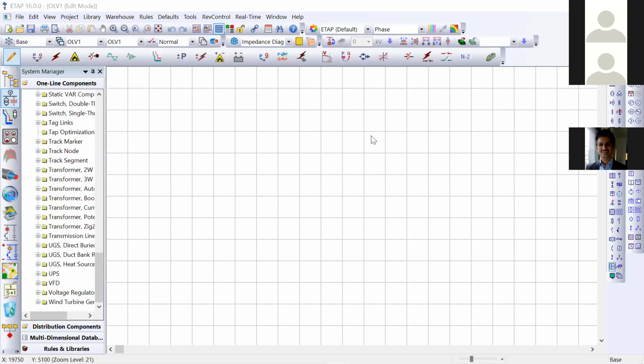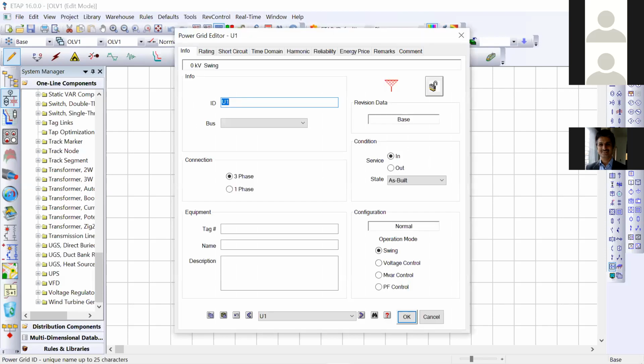Okay, so let us start creating one single line diagram. First of all, we will take up the source. Generally we start with the power grid because all our systems are connected to the power grid. So we'll take the power grid first. We'll double click it to configure it. Utility company source. It's a three-phase connection. You can always go with single-phase connection for microgrid creations. Then whether it is a swing bus, voltage control bus, MVAR control, or PF control bus, that you have to specify. Rating you have to specify.